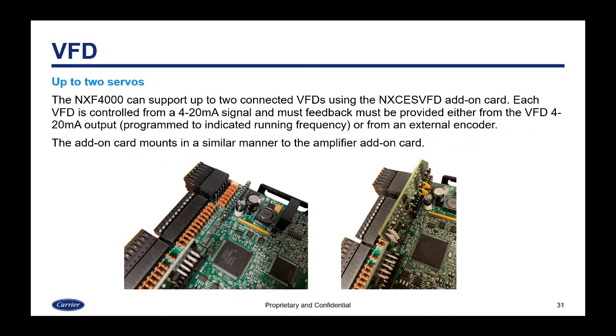With the VFD, the NXF4000 can support up to 2 connected VFDs using the NXCES VFD add-on card. Each VFD is controlled from a 4 to 20 milliamp signal and must provide feedback from either the VFD's 4 to 20 milliamp output or from an external encoder. The add-on card mounts in a similar manner to the amplifier add-on cards. You remove the cover, fit the NXCES VFD. There's also a presentation on interfacing a VFD with the Nexus systems available on the YouTube channel for a lot more detail on that, as well as how to connect the encoder.